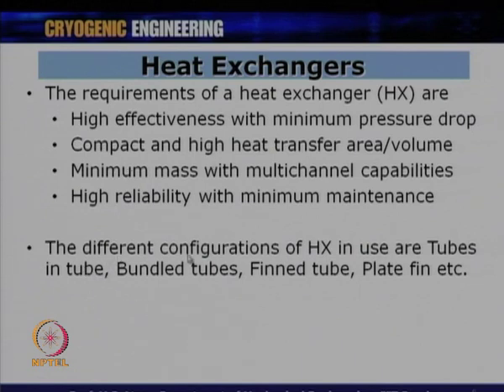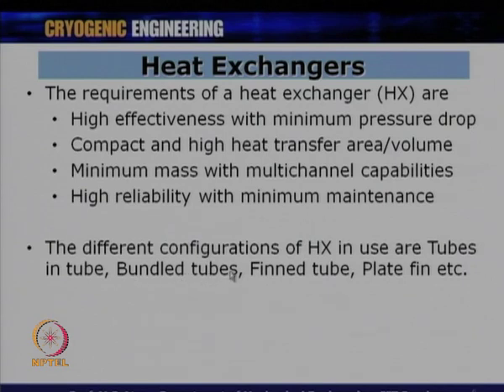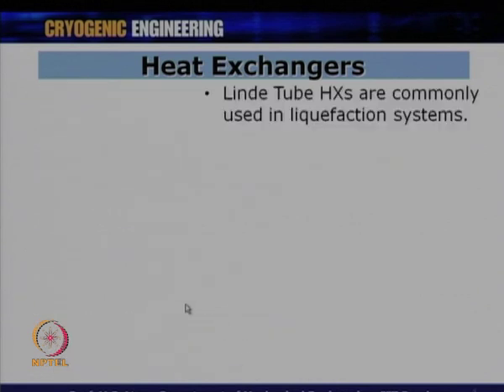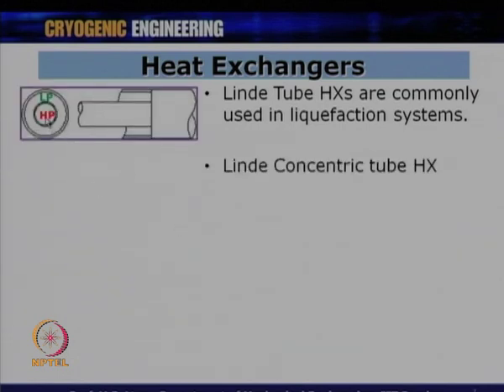Different configurations of cryogenic heat exchangers include tube-in-tube, bundle tubes, fin tubes, and plate-fin heat exchangers. Heat exchangers can be two-fluid or three-fluid types depending on the cycle. The Linde tube heat exchangers, invented and used by Linde, are commonly used in liquefaction systems. In a tube-in-tube configuration, the high-pressure gas goes inside the tube and the low-pressure gas flows over the tube — a Linde concentric tube heat exchanger.